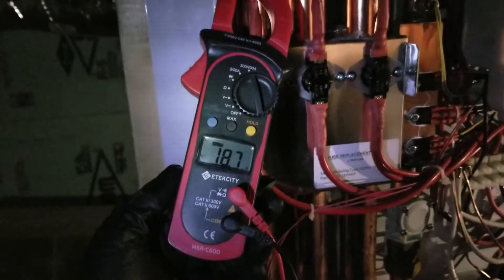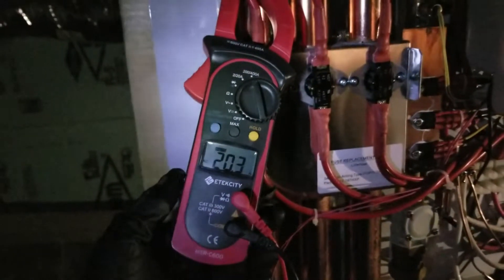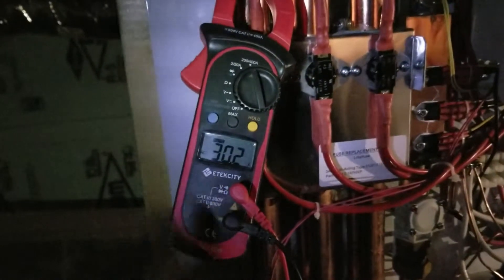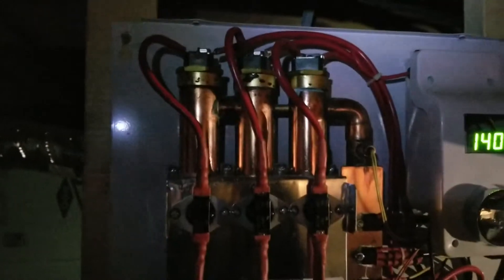You have about 16 amps on another stage. They'll kick up to 30 if you're using a sink and a shower at the same time, or two showers at once. But if you had an element reading zero, that means that element in the unit would be bad. On this unit there are three of them — hope that helps, thanks for watching.